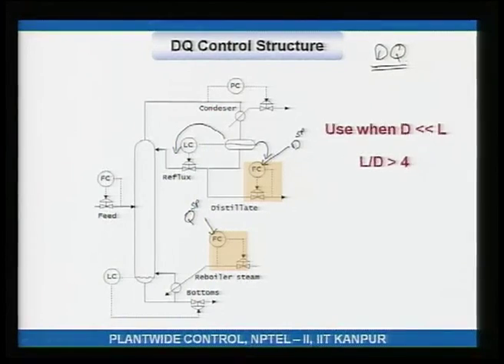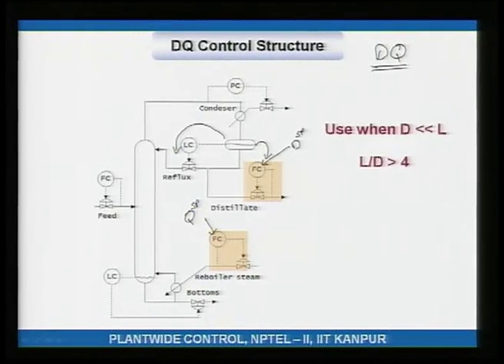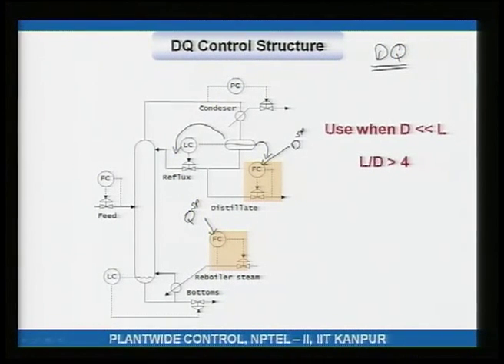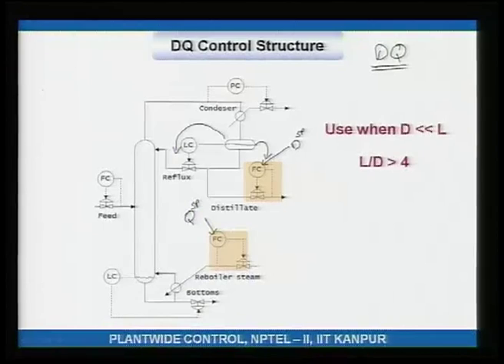After the level and pressure controllers are fixed, what remains for the operator are the distillate flow rate and the steam flow rate. This is called a material balance structure: when you change the distillate rate, you directly change the material balance around the column. For example, if the feed is 100 and you change the distillate from 50 to 60, you have directly changed the split occurring in the column.